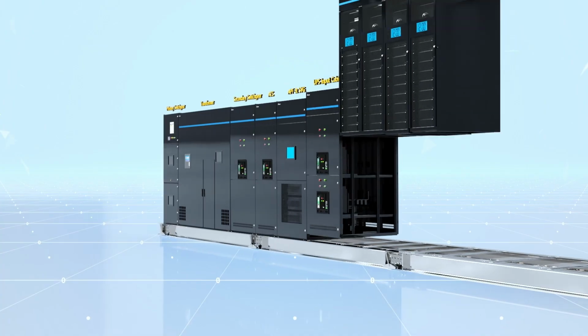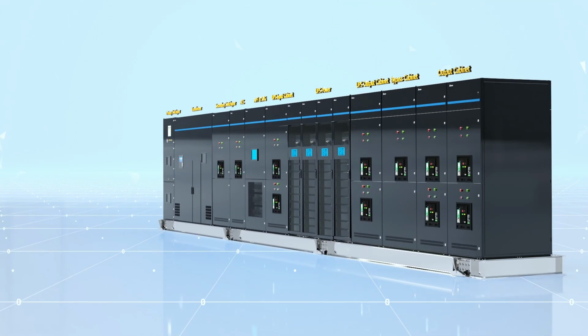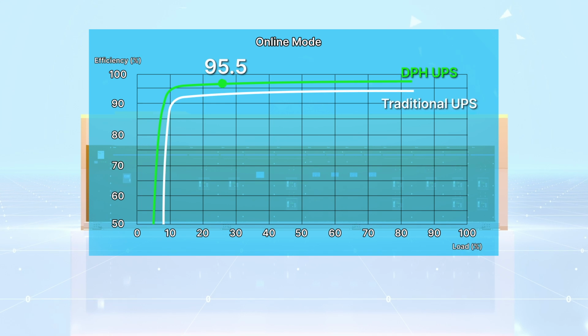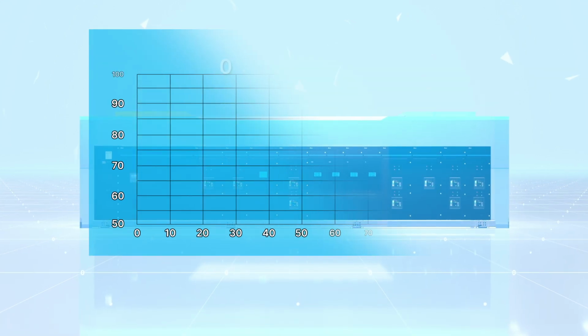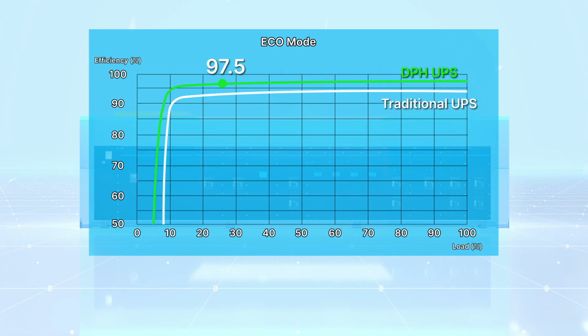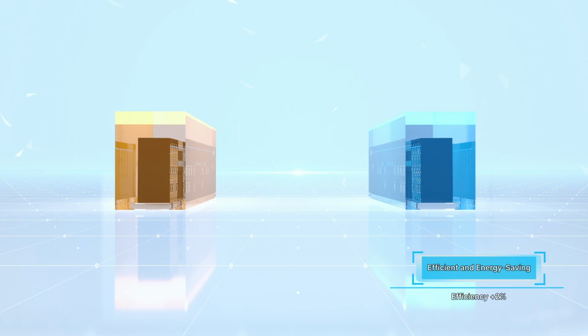Delta's HIP high-integration power supply module can adjust its operating mode as needed. In online mode, the system achieves an efficiency of up to 95.5%, while its supporting ECO mode can further improve efficiency to as high as 97.5%. This results in a 2% efficiency improvement compared to traditional UPS distribution systems.